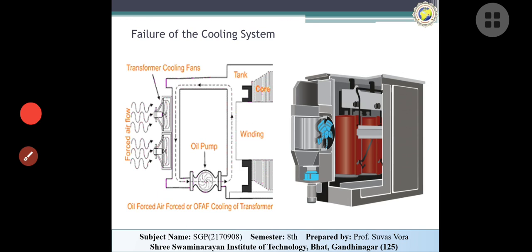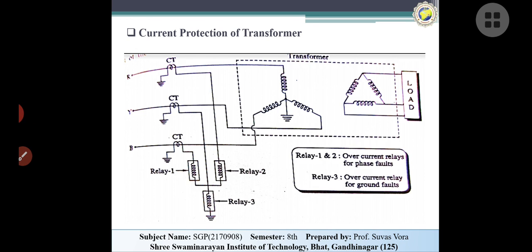Here you can see the damages to the transformer. Now the protection systems for transformers. We already studied that relay number 1 and relay number 2 are connected for the two phases. It means when there is a fault in a phase, relay 1 and relay 2 will operate. And another one is for the ground. When a ground fault occurs, this relay will operate. So the current protection of the transformer is applicable for phase to phase fault and ground fault also.